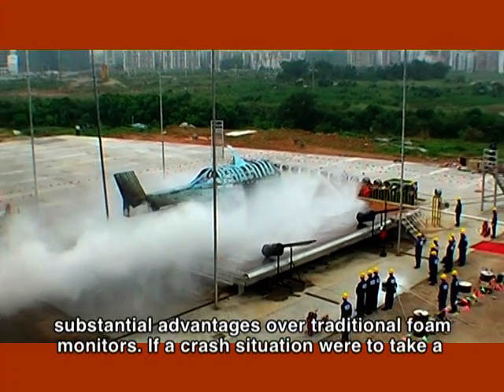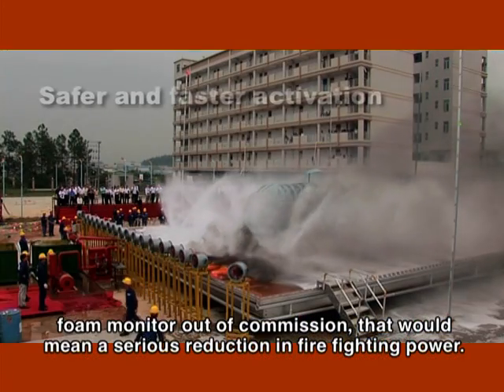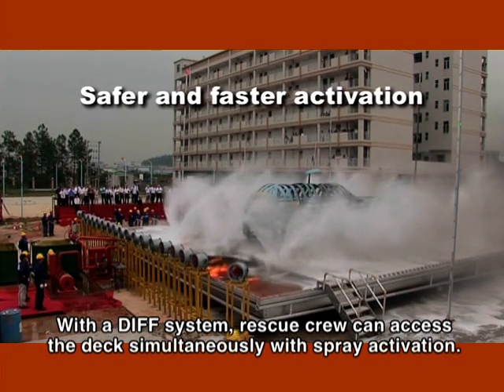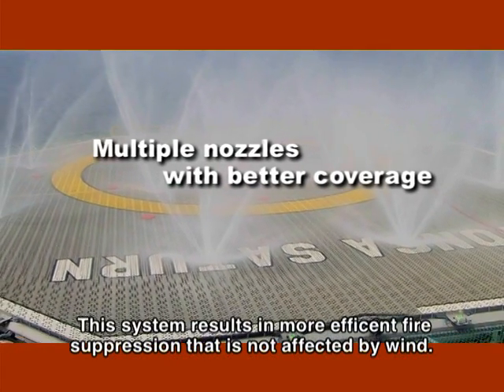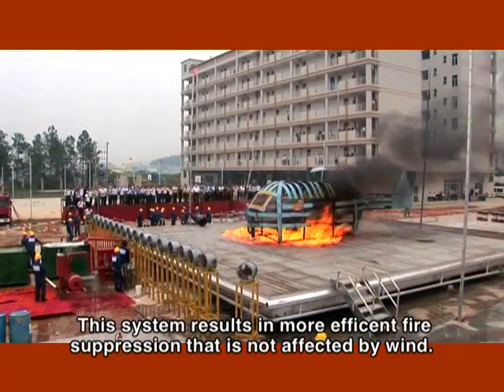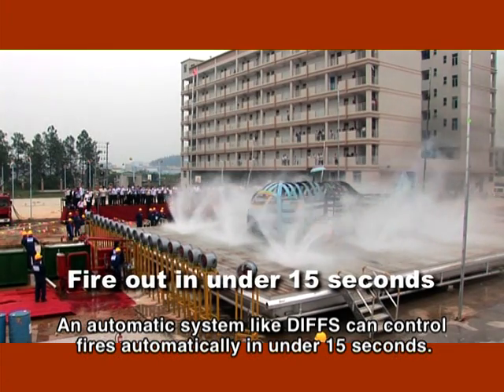If a crash situation were to take a foam monitor out of commission, that would mean a serious reduction in firefighting power. With a DIFFS system, rescue crew can access the deck simultaneously with spray activation. The multiple nozzles compensate for debris blocking individual nozzles, resulting in more efficient fire suppression that is not affected by wind. An automatic system like DIFFS can control fires in under 15 seconds.